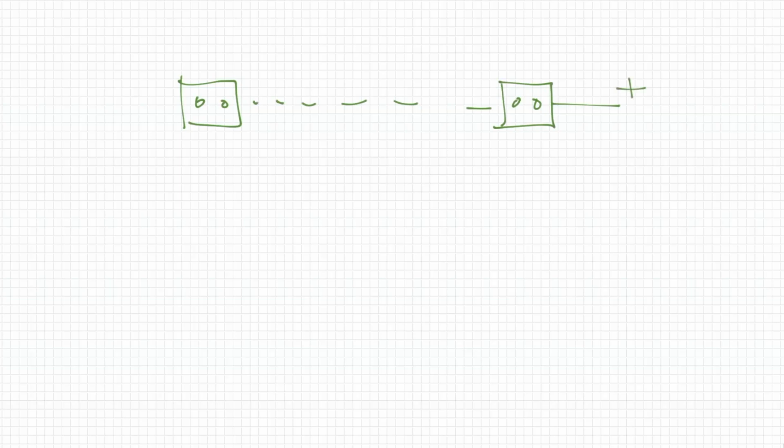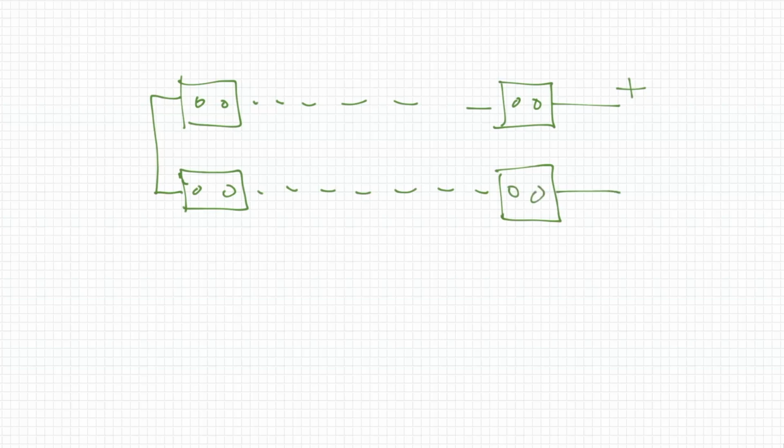So for midpoint voltage monitoring in a battery bank, it can't be in the battery enclosure, can it be on the outside of the box? What is typically done in, say, a larger installation of cells is, I'm looking in plan view, so this might be our positive. And then we may have a return string. So what you're looking at here is looking down onto the system. So let's say this is a nominal 120 volt system.